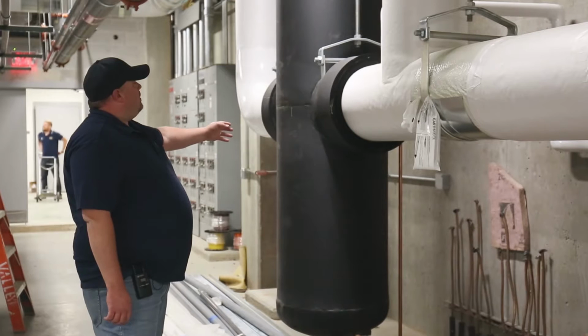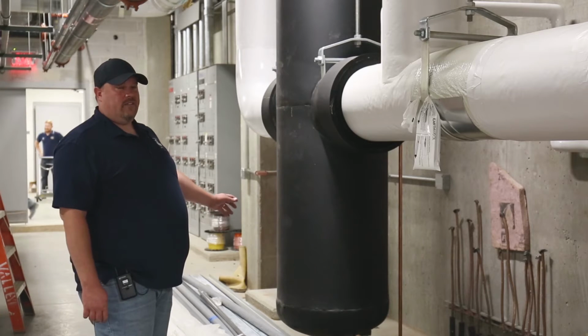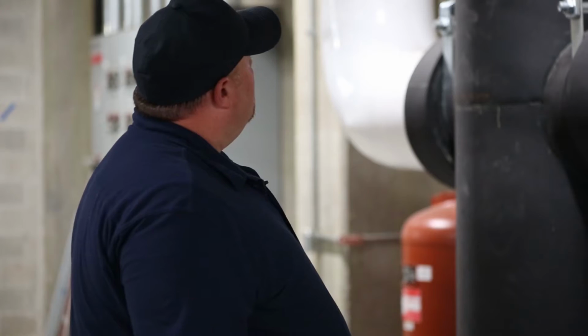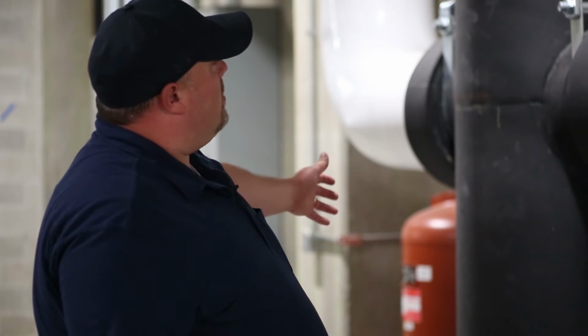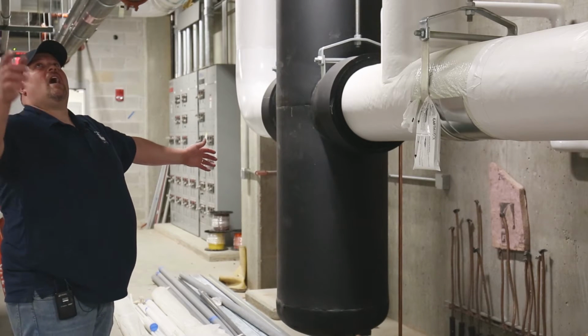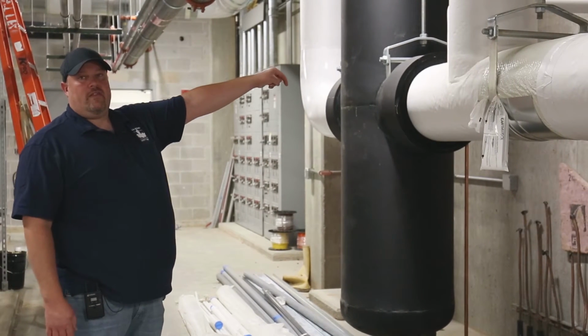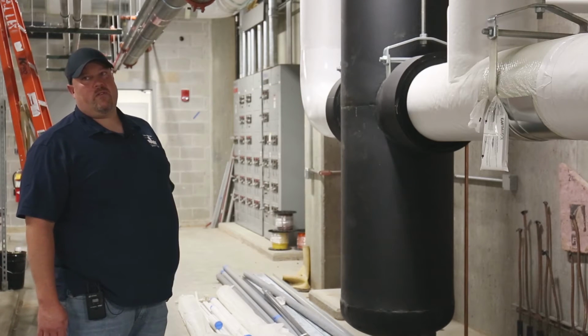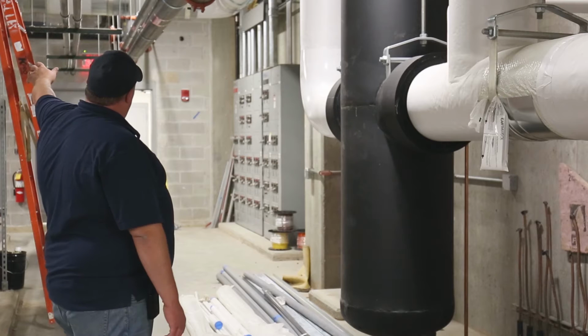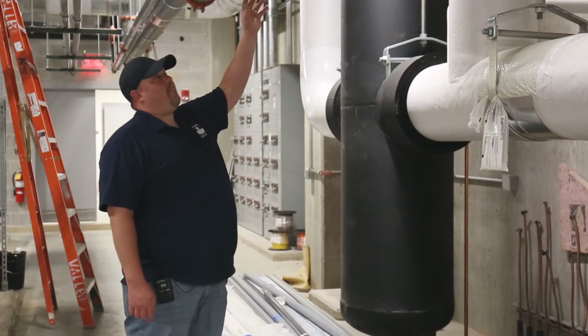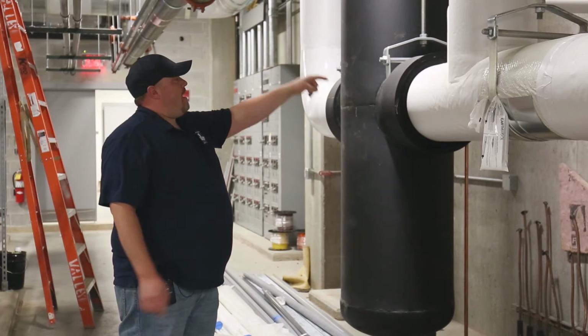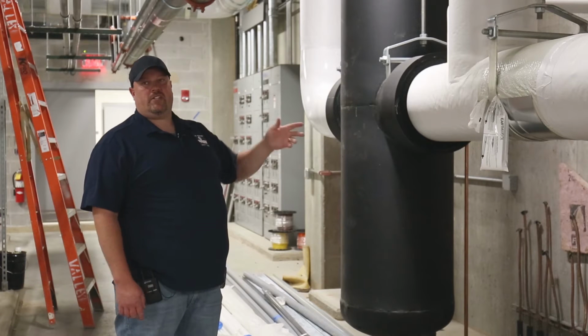As the chilled water system enters the building, it immediately goes through an air and dirt separator that requires a 1 month interval blowdown and the 6 months required after that. So as it enters, it goes through a large air and dirt separator as it enters the building. It also has a common return pipe with a 12-inch check valve that prevents any deadhead through the building. It proceeds on over to the 12-inch chilled water pumps with 3 in series. And here above we have a 12-inch check valve that allows the circulation to come back down to the supply from the return to allow the circulation through the building.